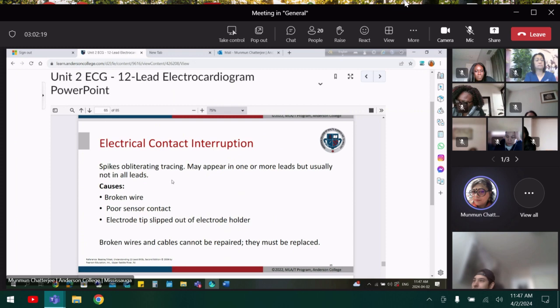In the ECG machine, you are probably getting all of them, only V6 you are getting that line. Why? Because the V6 electrode is not properly connected or not able to pick up the signals from the area you are going to connect from the heart to the machine.